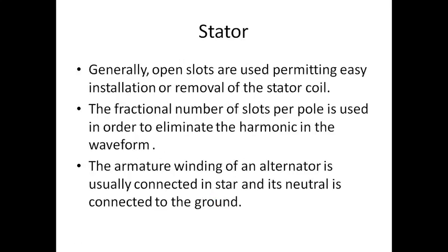Generally open slots are used because they are very easy to remove. If some problem is there, I can easily remove and replace it. The fractional number of slots per pole is used to eliminate harmonics in the waveform. The armature winding of an alternator is usually connected in star and its neutral is connected to ground. Maximum alternators will be connected in a star connection.